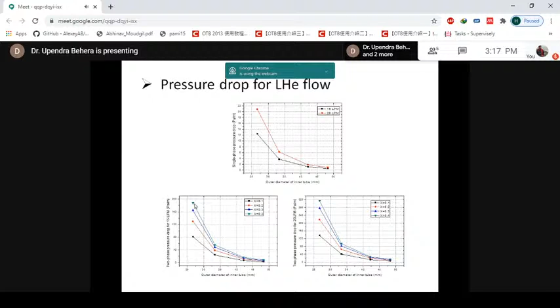Anyway, these data will be available or can be given on request, so I don't want to dwell on that. But I want to say that when your vapor fraction is increasing, your pressure drop is also increasing. You can see the black one is for 0.1 vapor fraction, meaning vapor content or void fraction, and the blue one is for 0.3, that means 30%. So once the void fraction is more, or the quantity of vapor in the inlet flow is more, the pressure drop is increasing.